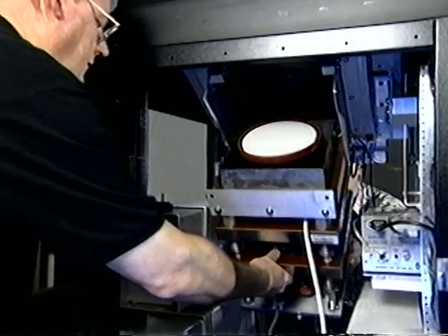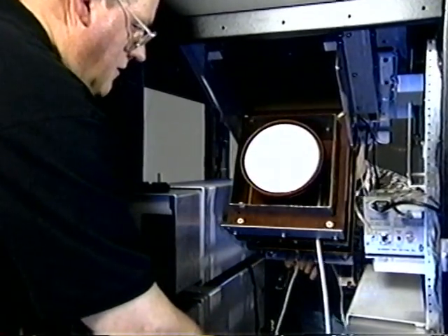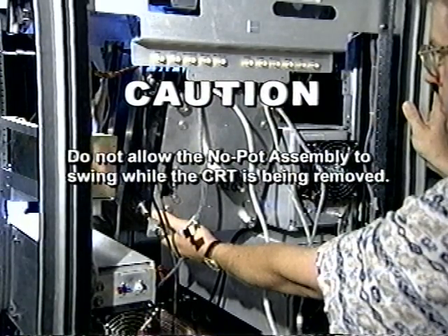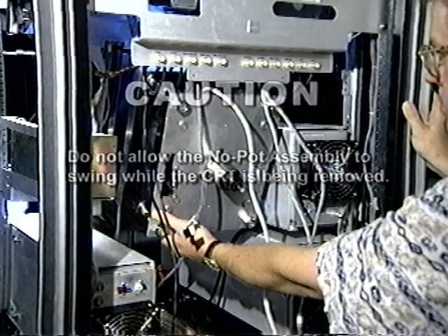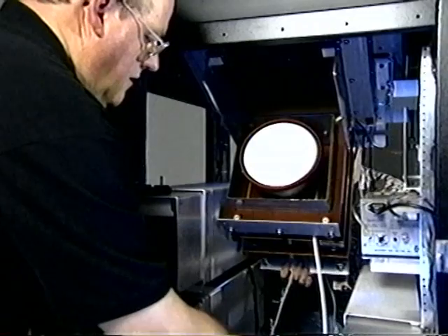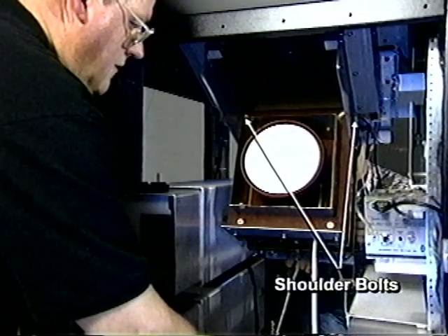Carefully pivot the no-pot assembly to the horizontal position. Caution! The assistant will have to hold the no-pot assembly in this position during the CRT removal. Do not allow the no-pot assembly to swing while the CRT is being removed, or the tube may be broken. The no-pot assembly pivots on two shoulder bolts.